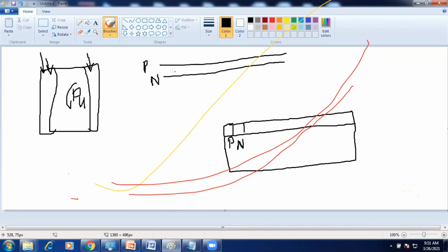From that 230 volt AC, I am going to connect directly to these pins, phase to phase and neutral to neutral. So it comes under with SMPS. By default, the PLC has an inbuilt SMPS, so it will automatically convert 230 volt AC to 24 volt DC. To protect the devices here, I am using circuit breakers. Just consider this is a circuit breaker.